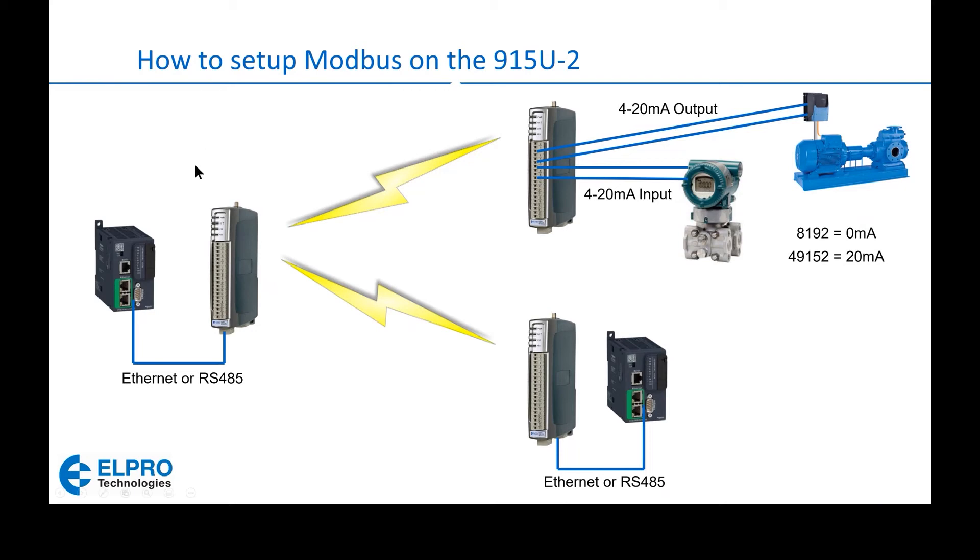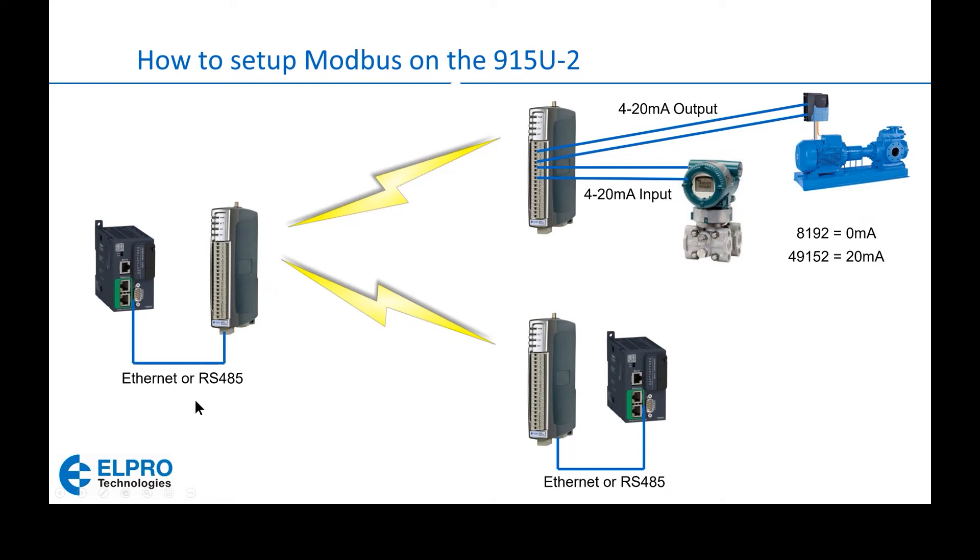On the left hand side we have our master radio communicating to a PLC using Modbus protocol. The protocol can be Modbus TCP if connected via Ethernet, or Modbus RTU if connected via RS485. The radio can function as either the Modbus TCP server or client, as well as with Modbus RTU the radio can function as the Modbus master or slave.